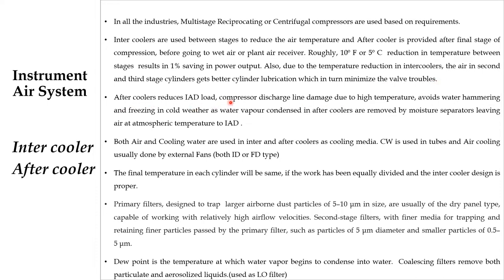The aftercooler reduces the instrument air dryer load. If the aftercooler is not there, the compressor discharge line can be damaged due to high temperature, and it will cause water hammering and freezing in cold weather. As water vapor is condensed in aftercoolers and removed by moisture separators, the air is left at atmospheric temperature before entering the instrument air dryer. So if hot air enters the plant air receiver without an aftercooler, it will damage the discharge line, cause water hammering and freezing. Aftercooler plays a vital role.